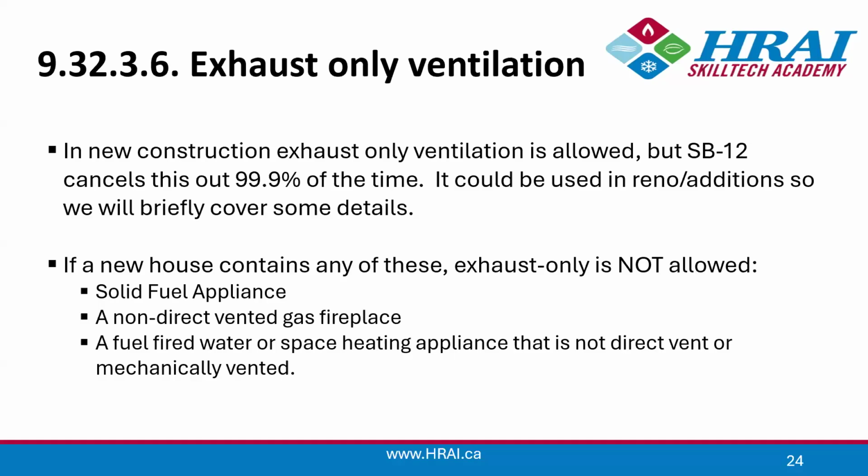So because of that harmonization, it's still available to us as well. So in new construction, it's allowed, and of course I'm just going to read the slide there, but I basically just said that. So if a new house contains any of these 3 items, exhaust only is not allowed. So we're back to that solid fuel appliance. So wood burning fireplaces, wood stoves, pellet stoves fall into that same category. That's a solid fuel appliance. You can't have exhaust only ventilation. So pressure is an issue, and that's how we deal with pressure.